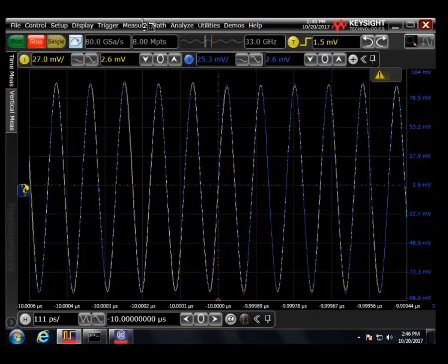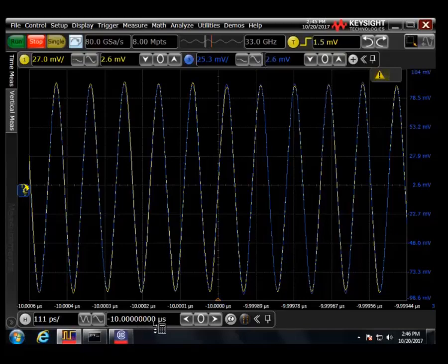So in this case, what I've done is I've zoomed in on a specific pulse after doing our single acquisition. So you can see by my time on the x-axis here, I'm at one of the pulses that's basically negative 10 microseconds off of the main trigger point. So I'm catching this particular pulse, and I started here because you can see that the phase between the two pulses is effectively lined up on each other. So we have a very, very good agreement here.